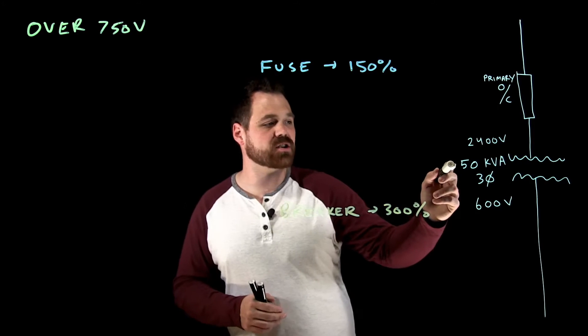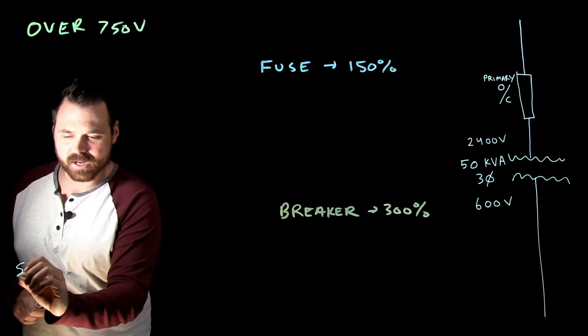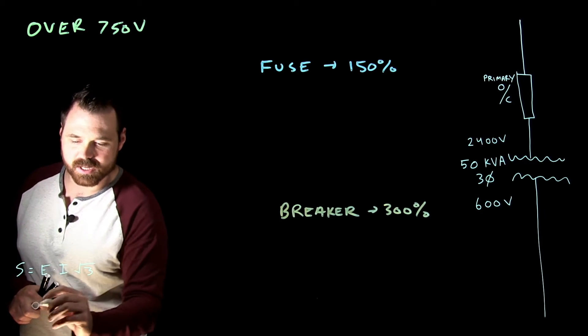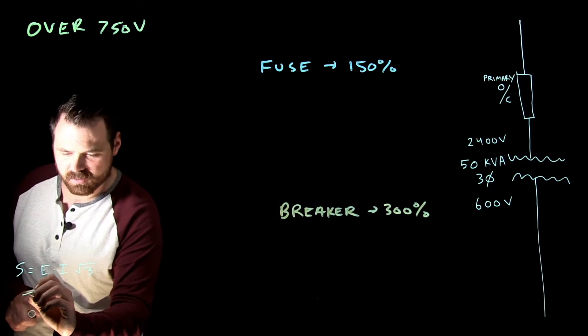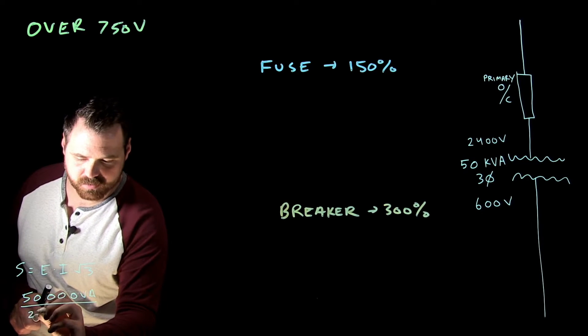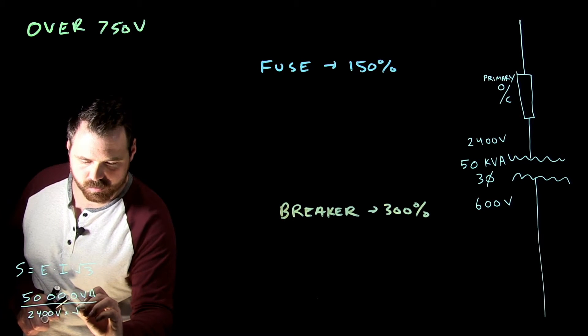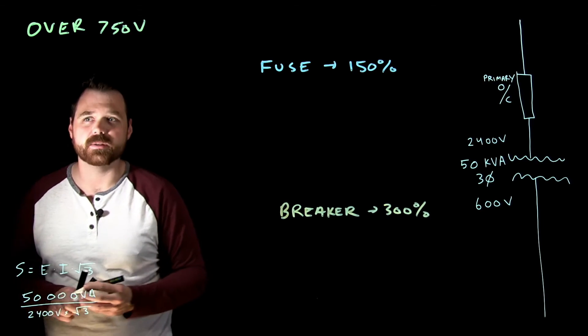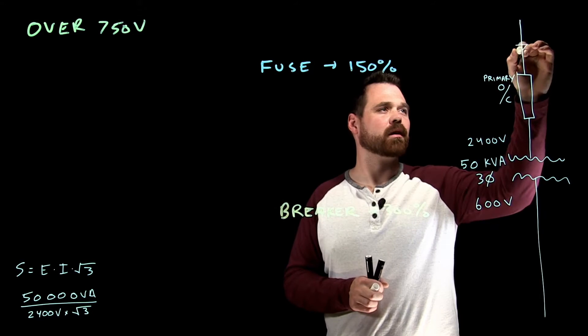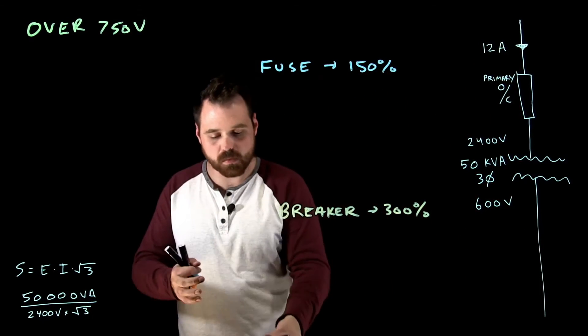So I've got a 50 kVA transformer, it's three-phase, and I'm at 2400 volts. So I'm going to take my formula S equals E times I times root three, quickly transpose this. So what this ends up giving me is a primary current here of 12 amps.